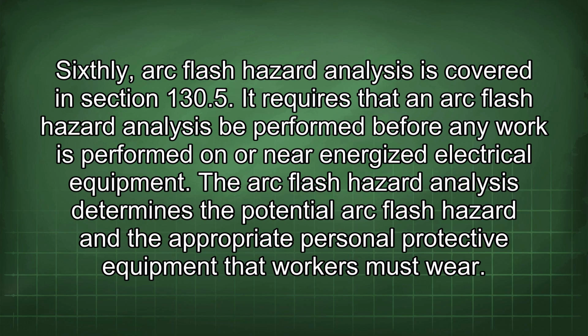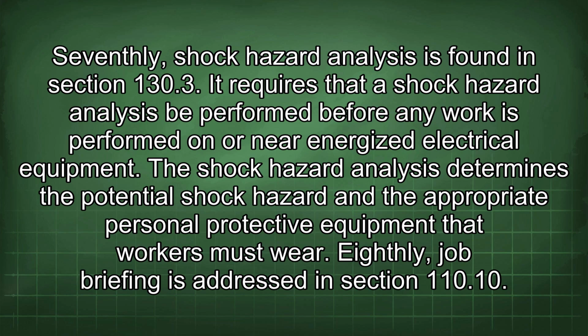Sixthly, arc flash hazard analysis is covered in Section 130.5. It requires that an arc flash hazard analysis be performed before any work is performed on or near energized electrical equipment. The arc flash hazard analysis determines the potential arc flash hazard and the appropriate personal protective equipment that workers must wear. Seventhly, shock hazard analysis is found in Section 130.3. It requires that a shock hazard analysis be performed before any work is performed on or near energized electrical equipment. The shock hazard analysis determines the potential shock hazard and the appropriate personal protective equipment that workers must wear.